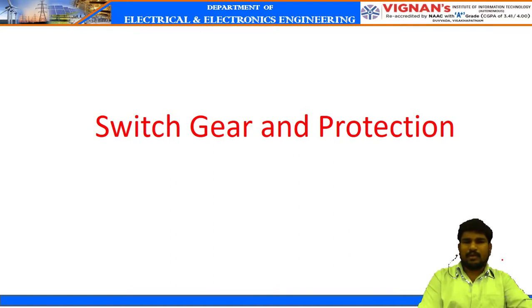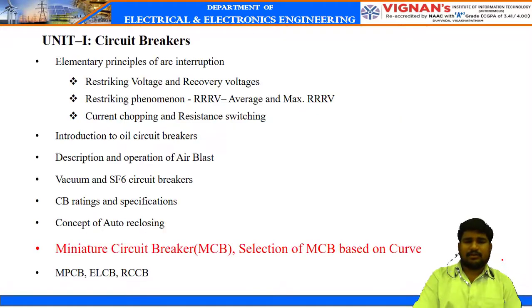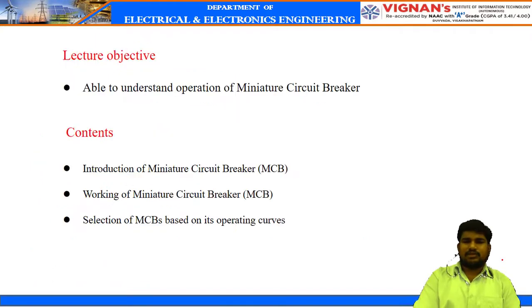For below 1 kV, what circuit breakers will we use? Those are MCBs and MCCBs. For earth leakage protection, we will use the earth leakage circuit breaker and RCCB. In this class, we will discuss miniature circuit breakers. At the end of this session, you will get the basic idea of the operation and working of a miniature circuit breaker, and the selection of MCBs based on their operating curves.